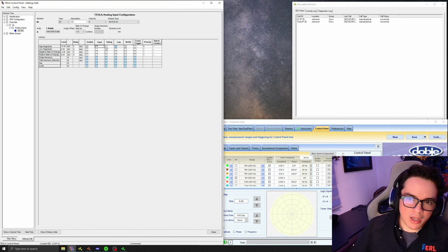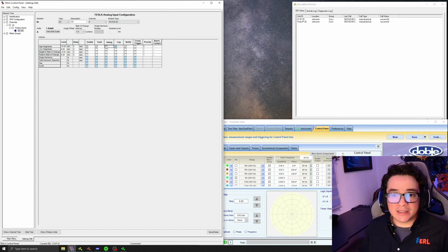I'm going to be creating a fault record, or if I wanted to create a combined record, I would have to also select the other checkbox of swing. What's the difference between fault record and swings? Faults are the transient records, which are of high speed, from 8 seconds to the back and up to 60 seconds up front of post-fault time, and also with a 32 samples per cycle speed up to a 384 samples per cycle speed.